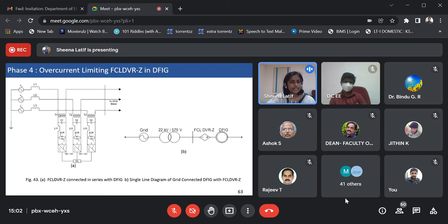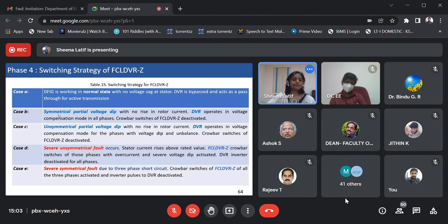In the FCL DVR impedance method, as we can see, it is a DVR itself which is connected between the grid and the DFIG stator. The only difference is we have two anti-parallel switches connected between the VSC and the filters. These anti-parallel switches will be triggered as soon as a severe fault current is detected in the corresponding phase, and the impedance L and C will come in parallel, and the effective impedance will appear on the stator side of the DFIG. The single line diagram of the grid connected DFIG with the FCL DVR impedance method is also shown for the 575 volt DFIG.